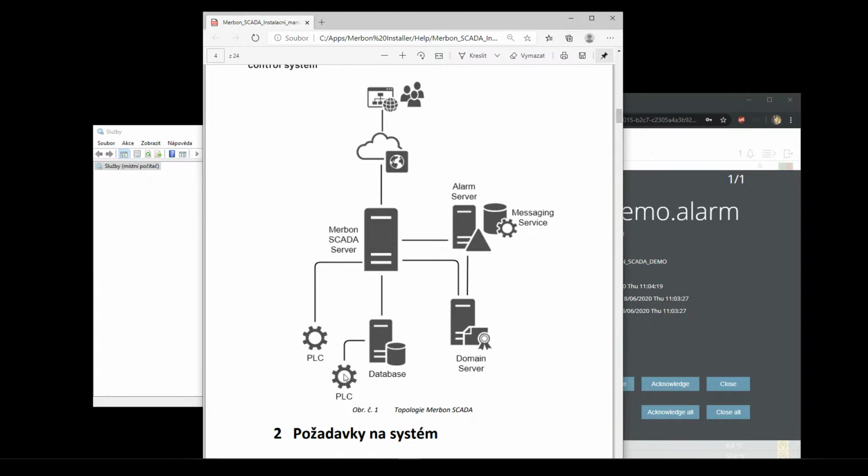I have to store the values, and I will wait when the database is online again, and then I will add all the values there. So in case you have some free internal memory in PLC, the PLC will save the data in its internal memory, and after the connection is restored, it will send the old data points from this period of connection problem to database.